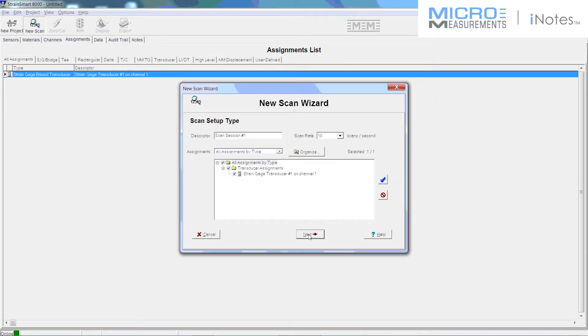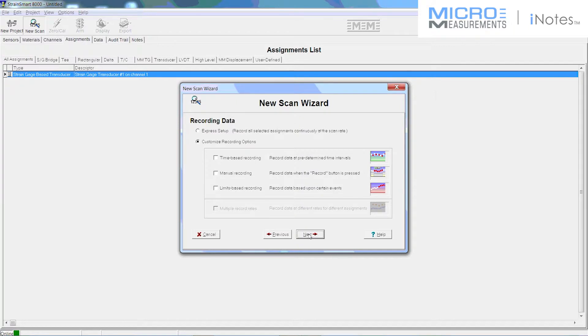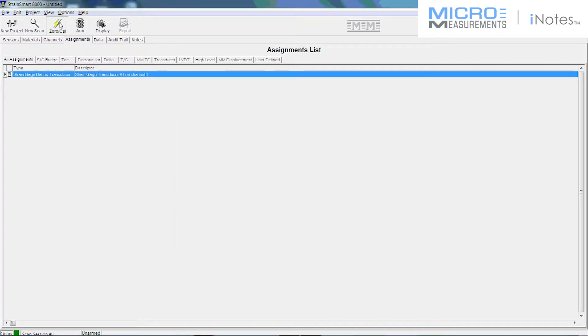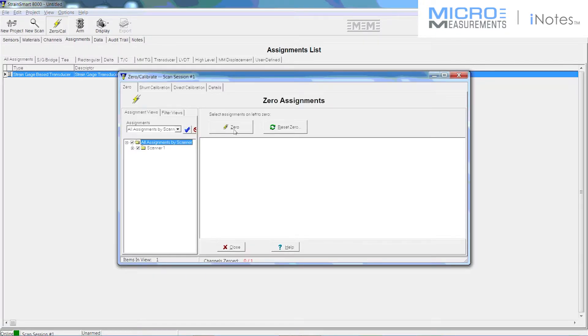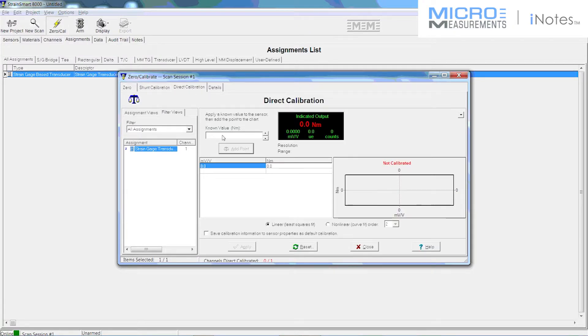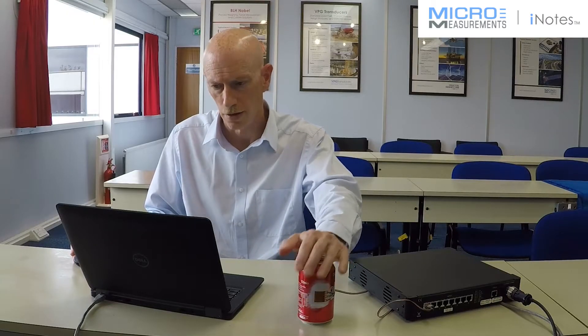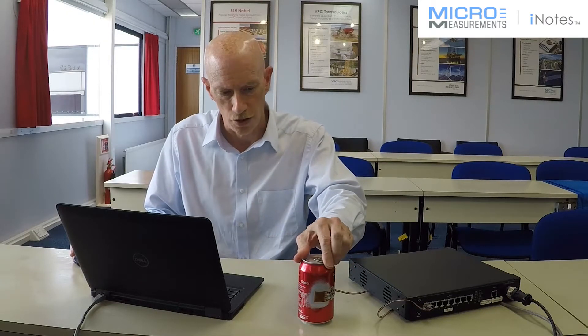I'm going to create a new scan. Scan rate of 10 samples per second. And record at 10 samples per second. Now I'm going to zero and calibrate. So zero just takes out any initial offset from the transducer. Now direct calibration is the part I'm really interested in. I can put in a known input to my transducer. Let's say I'm going to input 20 Newton meters.